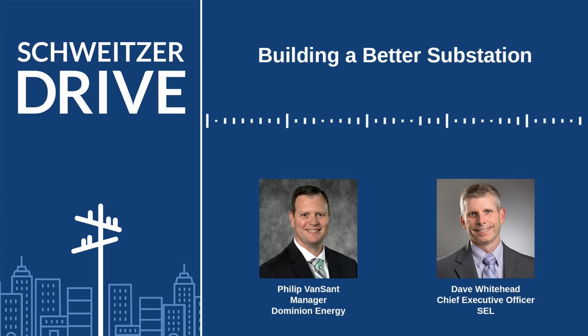Sure. So IEC 61850 is an international communication standard where you're converting your traditional analog signals, currents, voltages, or contact statuses to a digital format. And then that digital format gets sent to a centralized server network inside the control enclosure, and each device, protection device, control device, can subscribe to any data points that it needs. So we chose to go with 61850 because it allows you to condense the amount of protection and switching and controls on the control enclosure panels.